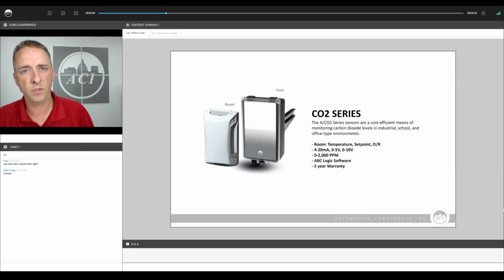I'd like to talk about this calibration software for a minute because it is a feature of our CO2 sensors that does separate them from competitive products, and there are some misperceptions and some confusion about what this software can do. It's called ABC logic, and what it does is trend the low level versus the high level of CO2 in a given space over a rolling 14-day average. So it trends that low level and high level of CO2 each day, the unoccupied versus the occupied levels of CO2, and then it calibrates based off that low level. It auto zeros itself based on the unoccupied levels of CO2 in the space, and it trends that over a 14-day average. So if there's any minor changes in the occupancy of a building, it takes that into consideration.